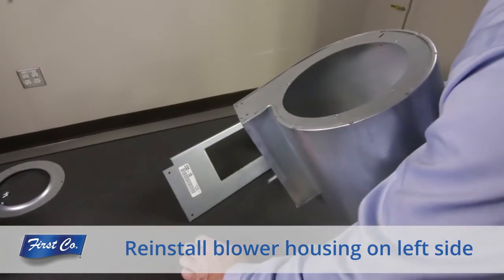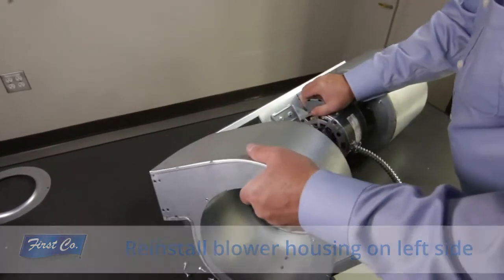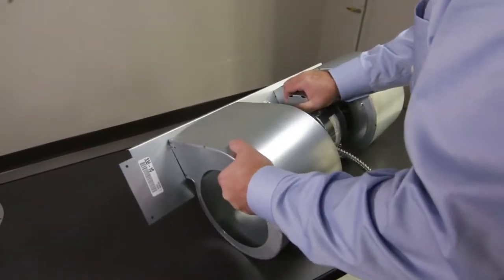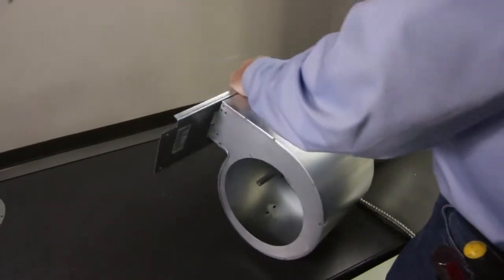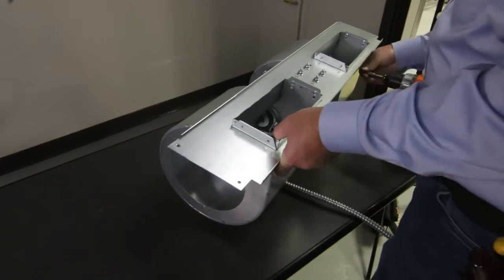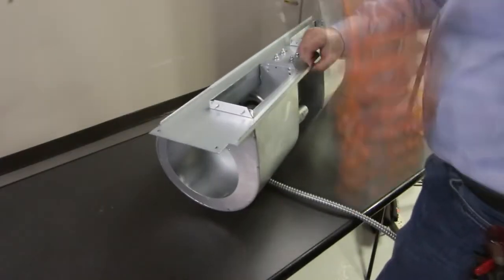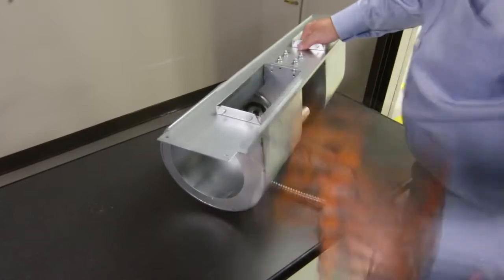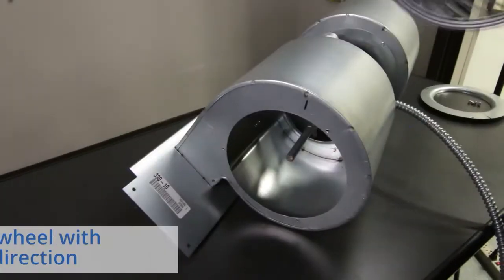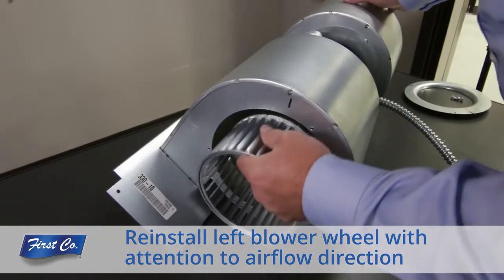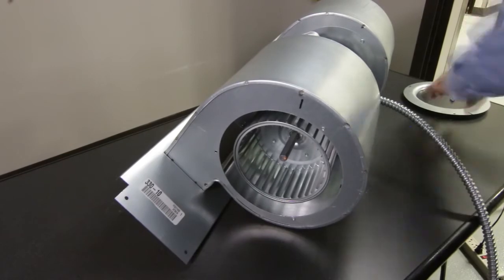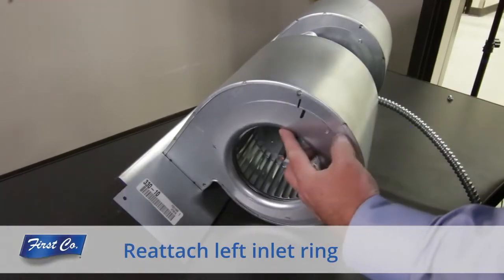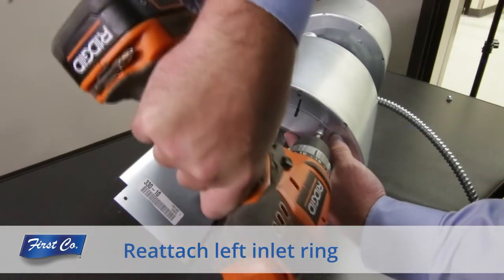Reinstall the blower housing on the left side that you removed earlier. Reinstall the left blower wheel paying attention to the airflow direction. Reattach the inlet ring lining up the reference marks you made earlier.